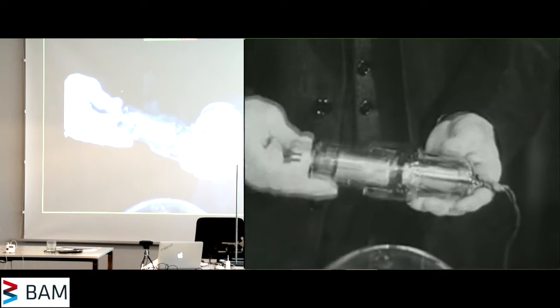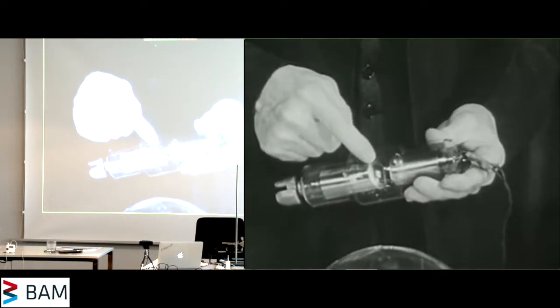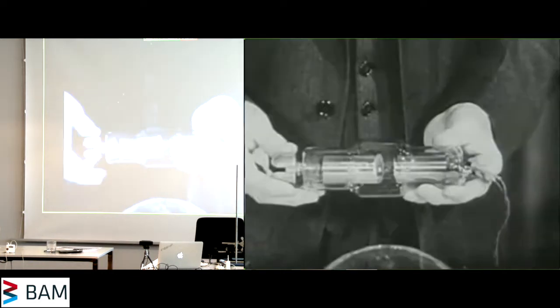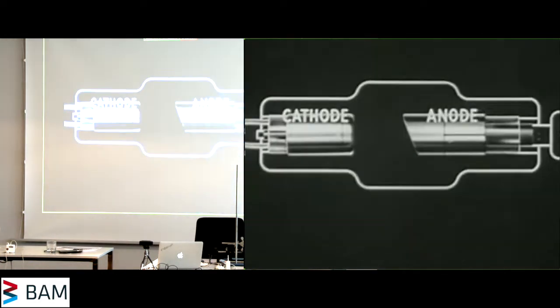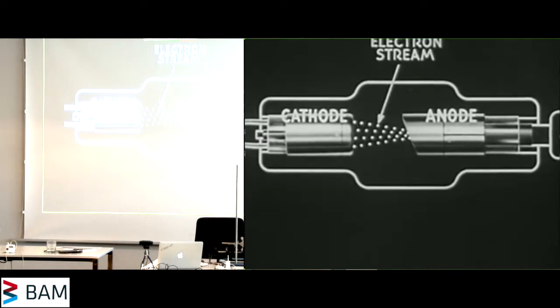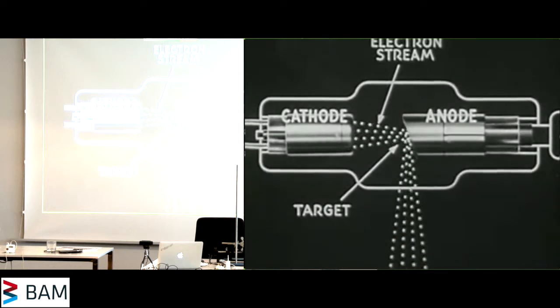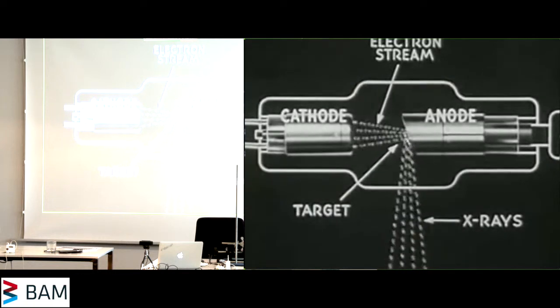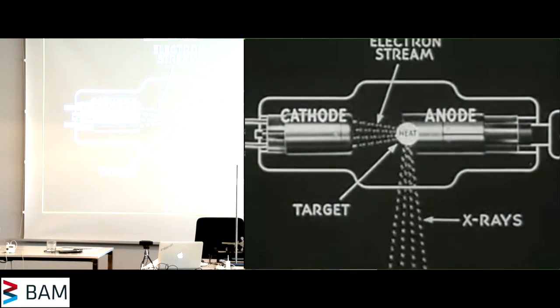The electron stream is focused to a very small spot on the target by the cup-shaped cathode structure. It seems that the electron stream striking the target at terrific velocity is stopped so violently that the electromagnetic radiation known as x-rays is produced. The efficiency of x-ray production is very low, and most of the energy of the electron stream goes to heat the target.